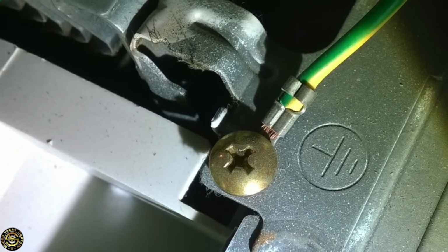If you remove that insulation and the cable comes in contact with something that's metallic, like the casing of an electric motor, for instance, that electric motor casing now becomes live. So for this reason, the casing is earthed. So a cable is connected to the outer casing and that is run to earth, run to ground or neutral. Remember, the electric always goes back to neutral. So what we do is we take a cable, we connect it to the outer casing, and then we run that cable to neutral or to ground. And that way, if someone touches that casing and the insulation has failed, they won't be electrocuted.